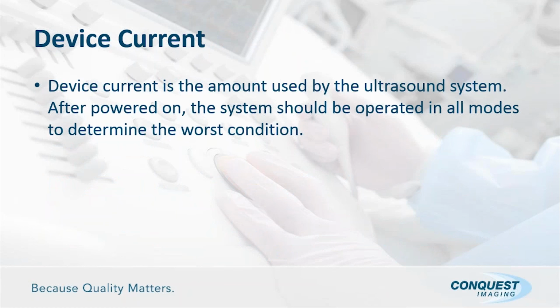Device current is the next thing we want to concern ourselves with. It's the amount used by the ultrasound system, and it needs to be, again, powered on and actively scanning. And one thing you should do is go ahead and enter all the different modes, your B mode, your color Doppler mode, your 2D mode, and determine which one gives you the worst condition or the highest reading in this case, and record that highest reading.